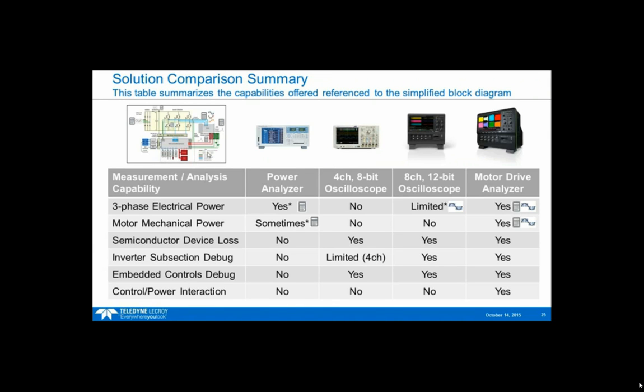So if we do a quick comparison here, this is all the different instrument types you might be familiar with: the power analyzer, the 4-channel scope, an 8-channel scope, and a motor drive analyzer. And these are the capabilities pictorially represented by this big simplified block diagram. And then these are the different types of areas in that block diagram. And again, a power analyzer, good for numbers, for 3-phase electrical power. The better ones incorporate motor power as well, but nothing else. 4-channel 8-bit scopes, really limited to embedded control system and limited inverter subsection debug. 8-channel scopes are better. At least you can see your power waveforms. And you do a much better job of debugging because you have more channels. But the motor drive analyzer combines the best of all those things. Gives you numbers and waveforms on 8 channels and lets you really dig around in any part of this block diagram and understand what the behavior of your system is.